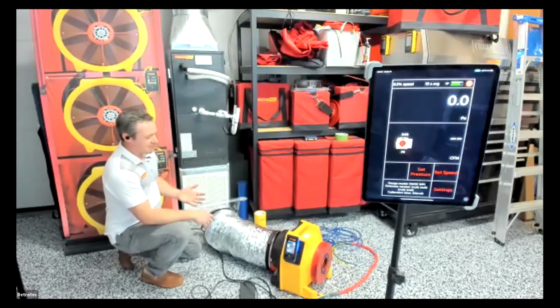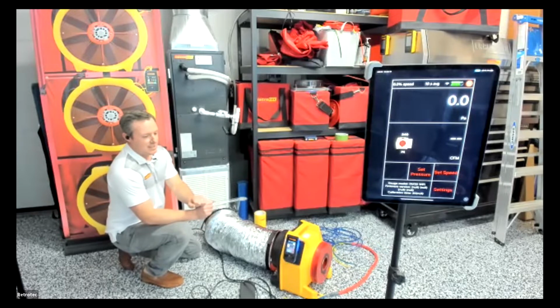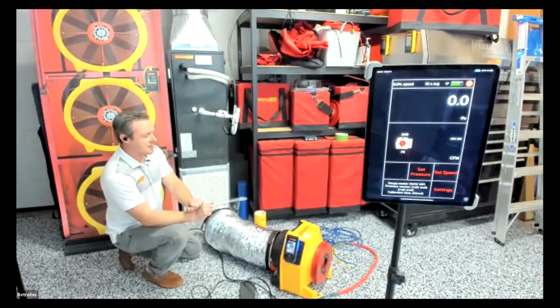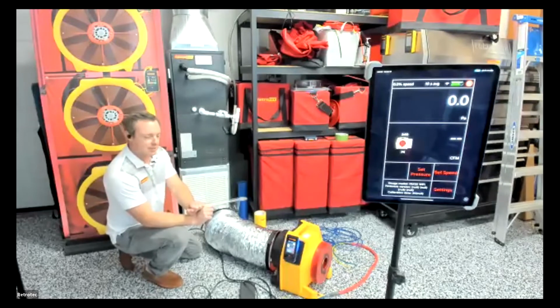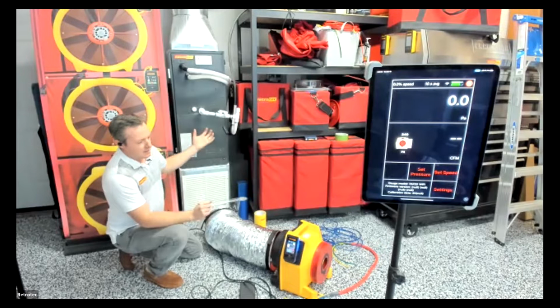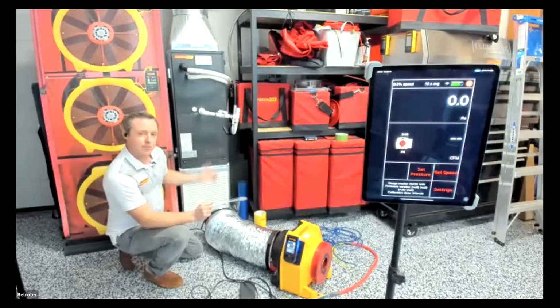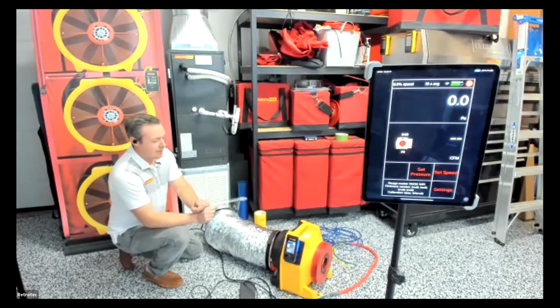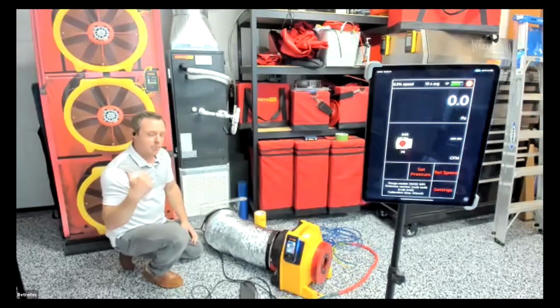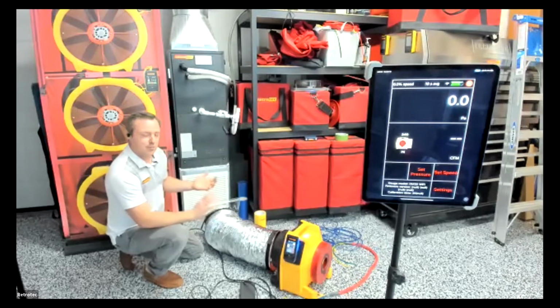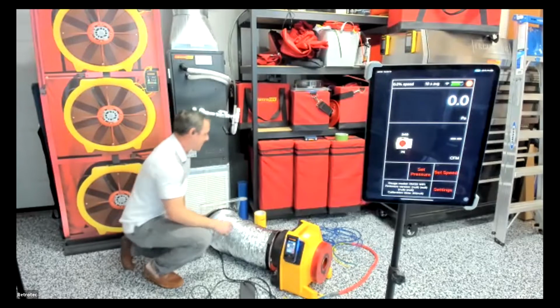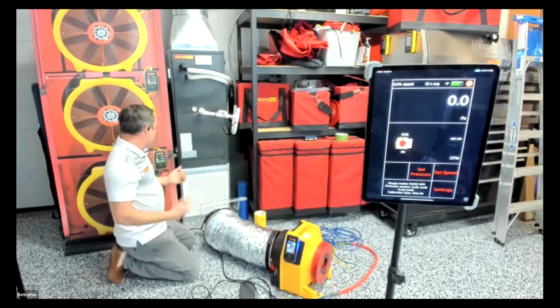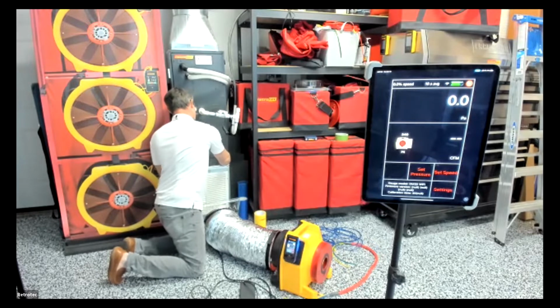But as we hook up this duct tester to the system and get it running, say we're going to depressurize the ducts, and we're going to be pulling air through the leaks of the duct system. And if we're pulling air from outside the envelope, we can pressurize the house a little bit that way, and the manometer is going to pick that up, and our reading is going to be a little funky. So that's why we want to have a door or window open, to balance that out and prevent the house from pressurizing. So, once we do that, we want to make sure we take the filter out.